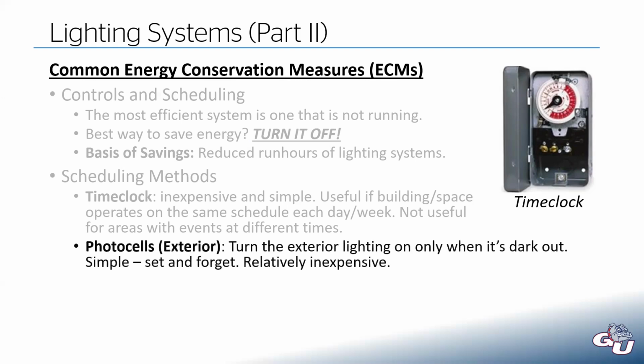If you have exterior lights that are outside, say in a parking lot, you can control those with what's called a photocell, which is really just a little sensor that detects light outside. And if it detects light, it breaks the circuit to the light fixtures and turns them off. And then as soon as it gets dark, that closes the circuit and then turns the lights on. So similar to the time clock, this is a very simple device. You buy it, install it, set and forget. Also pretty inexpensive. You can buy this stuff at your local hardware store.